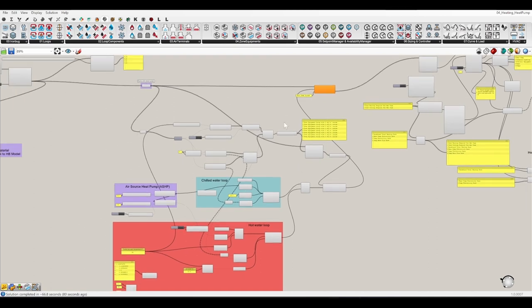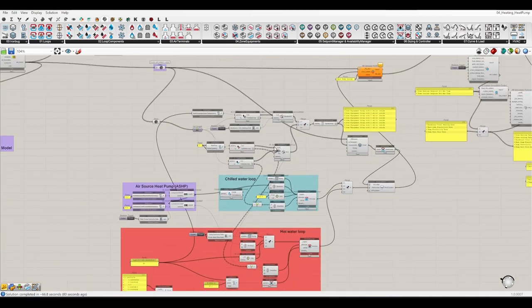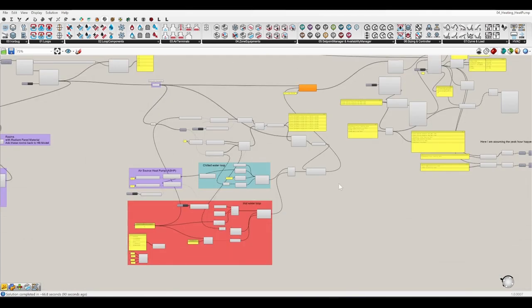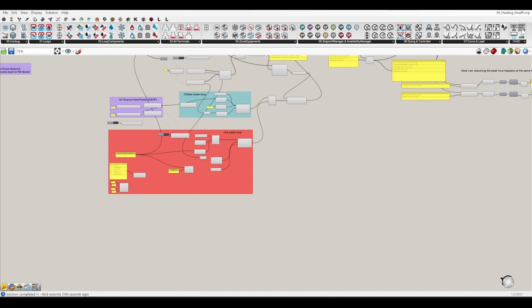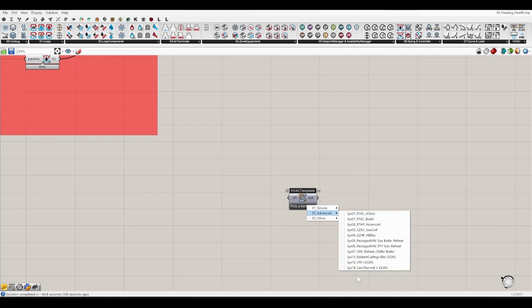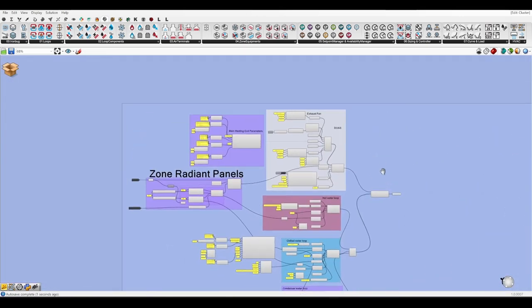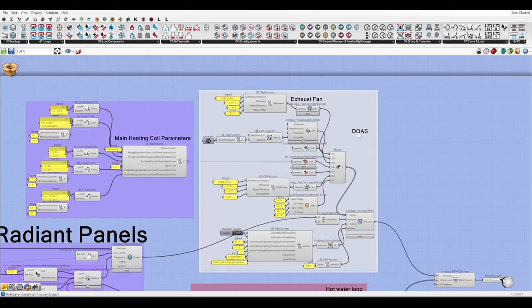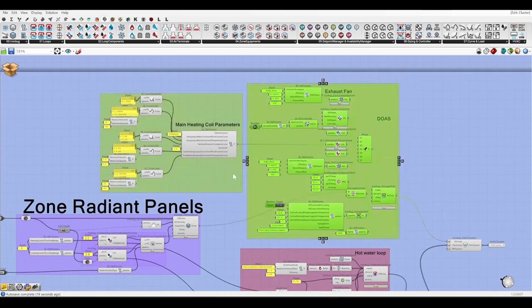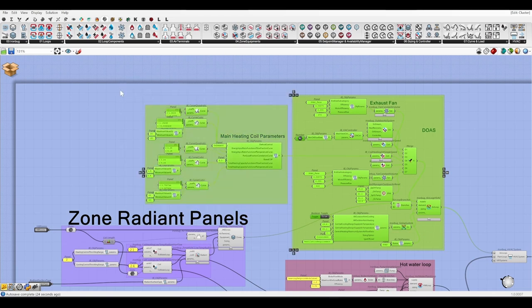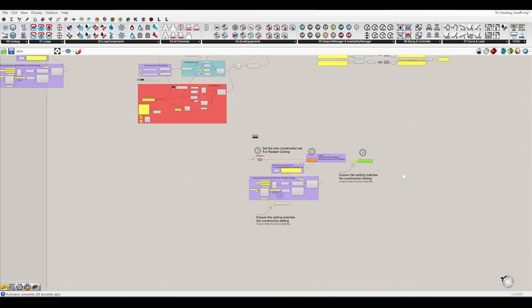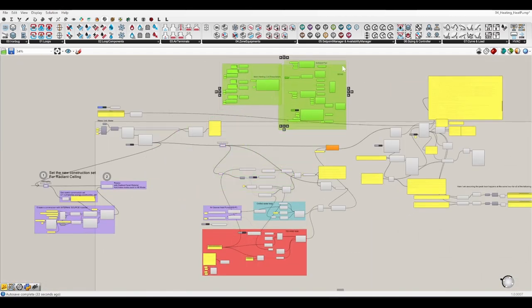Now let's see about adjusting the heating and cooling for these eight zones. What if we want to add a ventilation system? From the previous radiant ceiling template there is a DOAS — a Dedicated Outdoor Air System. Let's go inside the cluster and check it. A DOAS only provides fresh air for the zones; it doesn't handle any heating or cooling load. Let's copy this DOAS system and paste it.